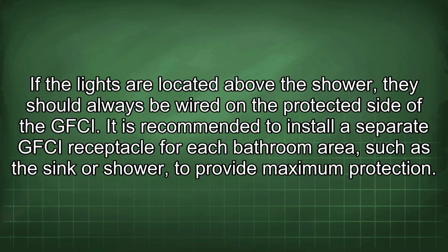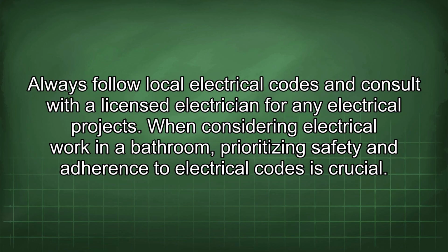If the lights are located above the shower, they should always be wired on the protected side of the GFCI. It is recommended to install a separate GFCI receptacle for each bathroom area, such as the sink or shower, to provide maximum protection. Always follow local electrical codes and consult with a licensed electrician for any electrical projects. When considering electrical work in a bathroom, prioritizing safety and adherence to electrical codes is crucial.